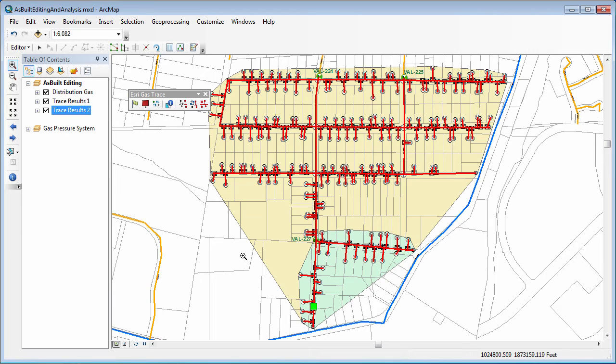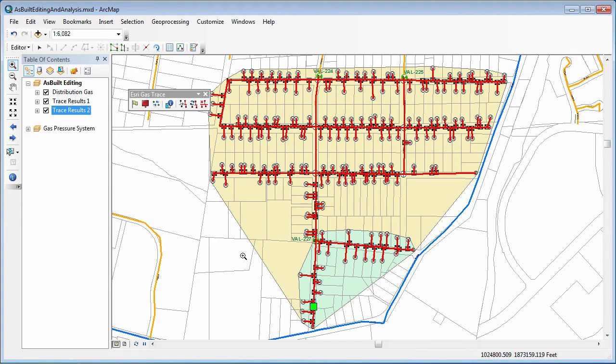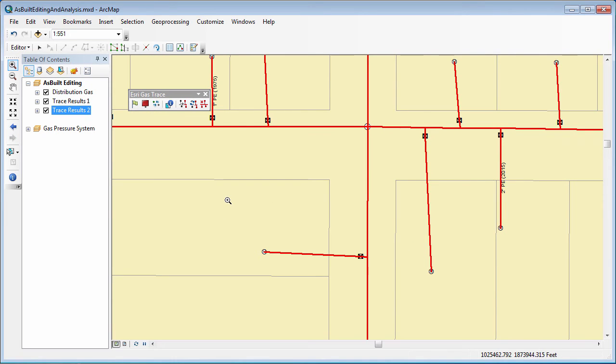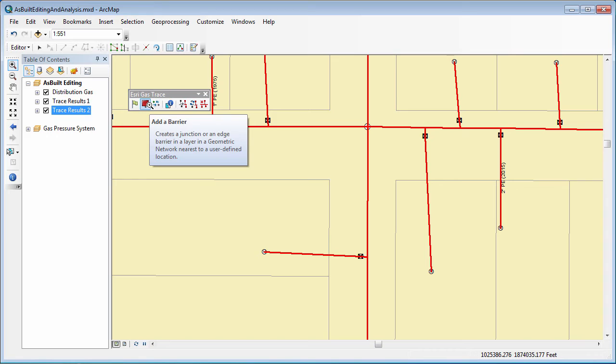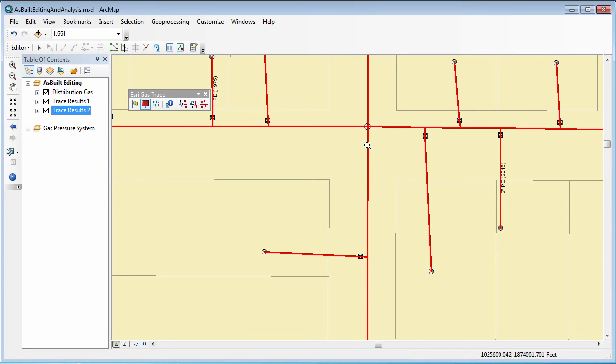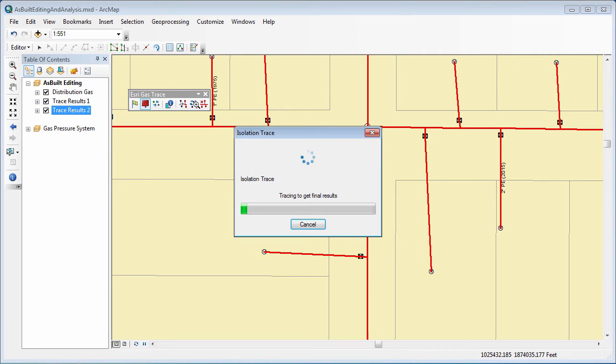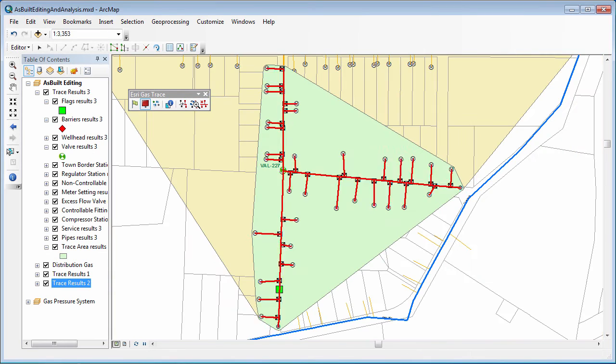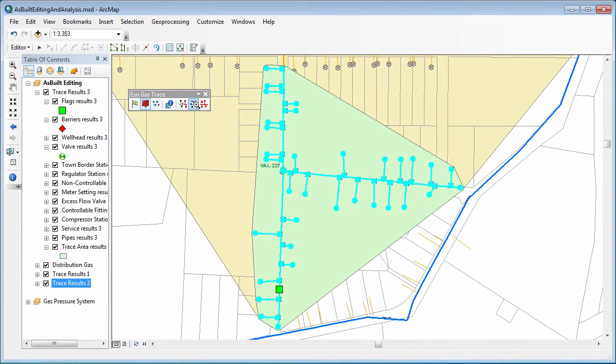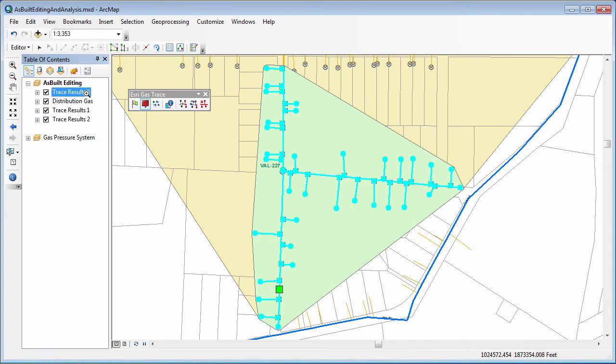The final piece that I wanted to show you is that there is the ability to place a squeeze off. So if we have plastic pipe, we can place a squeeze in the field, which acts as a temporary barrier to that trace. That would be sort of a third potential thing I would want to show within this trace. This is a well-known trace we've used in utilities for years. We're going to use this tool of adding a barrier, so this will act as a squeeze. Let's just say we can squeeze off this pipe here. You see the diamond feature placed there on the map. I'll place that and then one more time we'll rerun the connected isolation trace using the same start points that we used in our first traces.